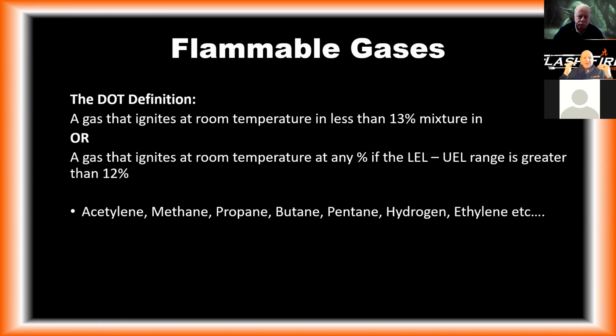So either we have a gas that can ignite at room air in less than a 13% mixture, meaning we don't need as much of it to ignite, or we have a gas that has such a wide range that the range between the LEL and UEL is greater than 12%. So these would be like acetylene, methane, propane, butane, pentane. And we've probably heard these all before.